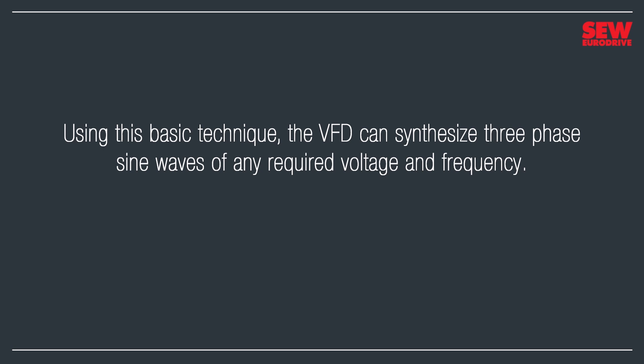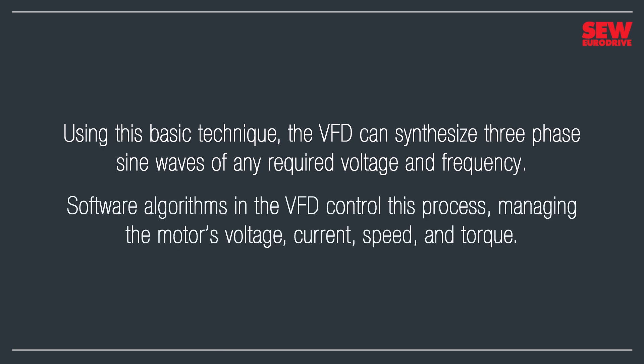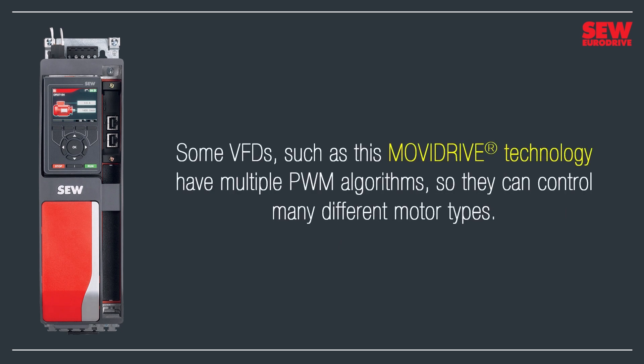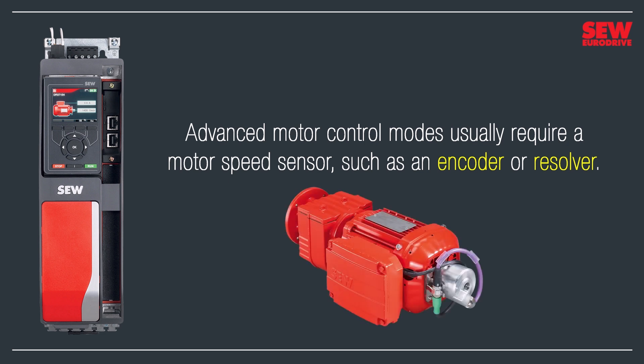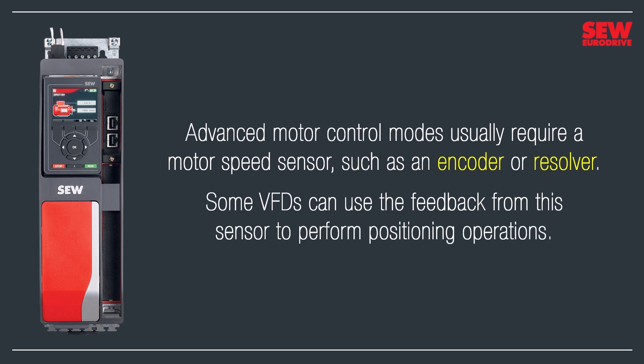Software algorithms in the VFD control this process, managing the motor's voltage, current, speed, and torque. Inexpensive VFDs may have just one simple algorithm, but some, like this MOVIDRIVE technology, have multiple PWM algorithms so they can control many different motor types. Advanced motor control modes usually require a motor speed sensor, such as an encoder or resolver. Some VFDs can use the feedback from this sensor to perform positioning operations.